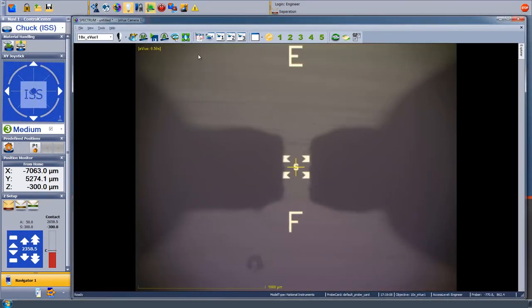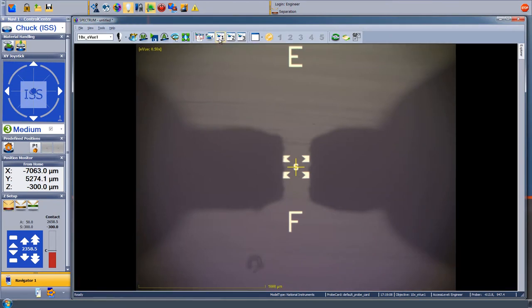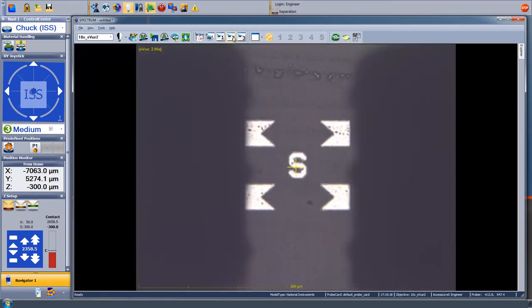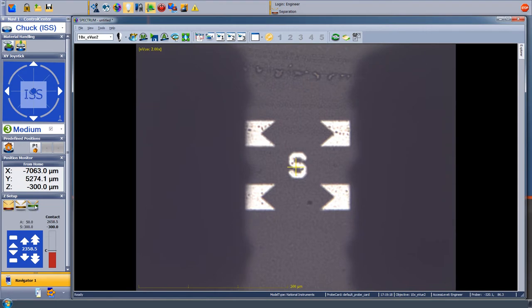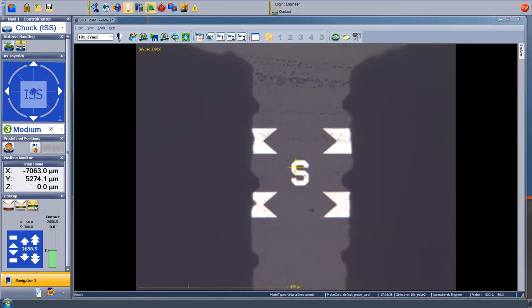When measuring up at millimeter wave frequencies, the probe placement and even how far you push down on the wafer must be very carefully controlled. To control that, we have special structures that help us set the height such that when we make contact with the substrate, the probe will skate a very precise amount.